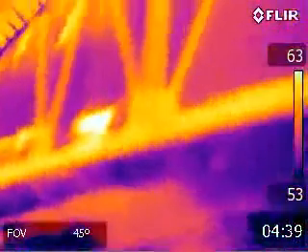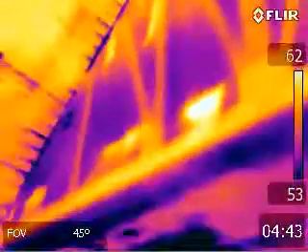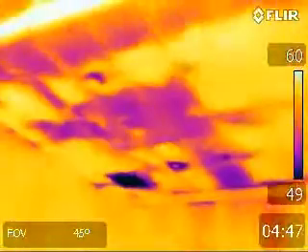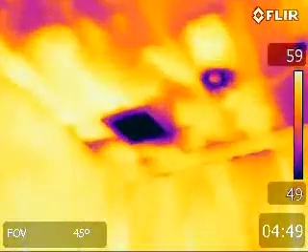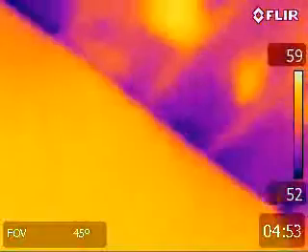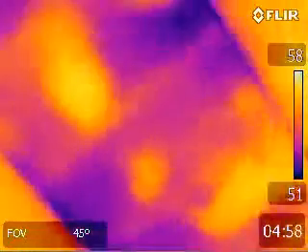There's also an air handler, a furnace in the attic with duct leakage occurring, which is also increasing the attic temperatures, causing a warm roof, which is the primary cause of icicles.